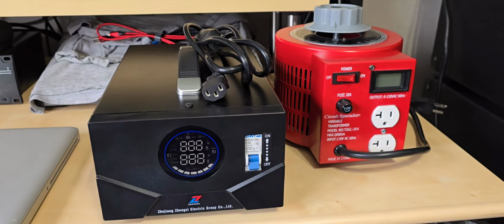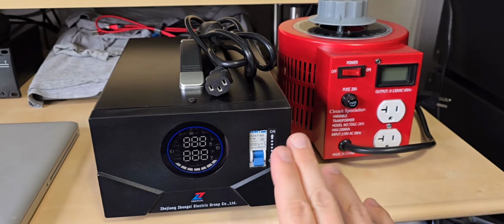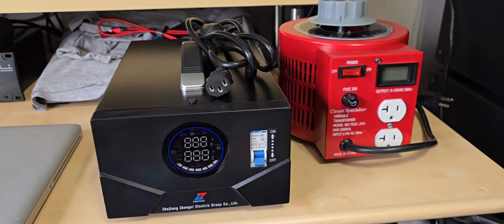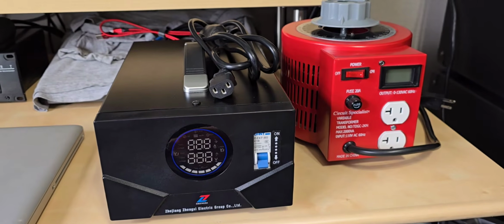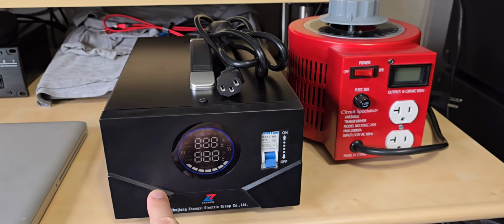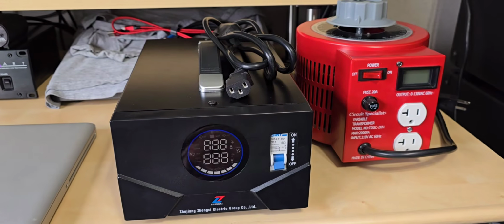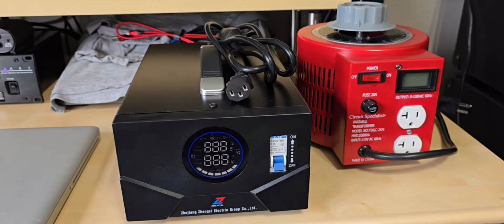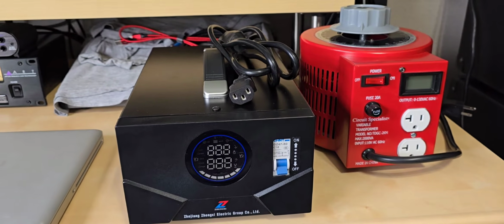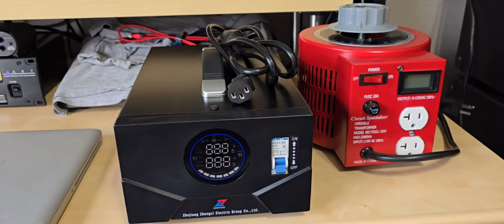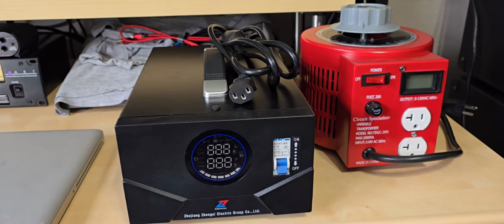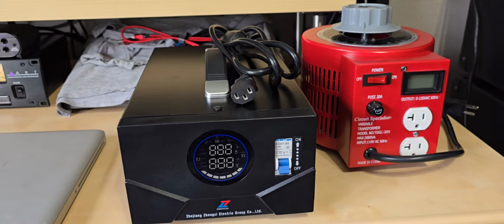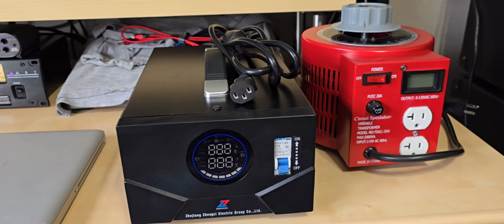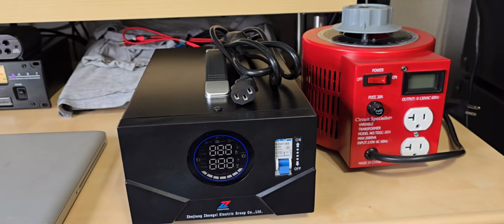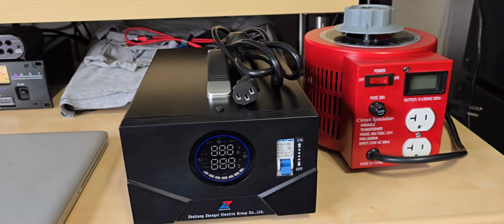I'm very happy now with the functionality because it is now working as described and advertised. To be fair, the 145 and 35 volts is considered voltage regulation, although it's not really effective in my opinion. The 132 and 105, as I mentioned, is a lot more reasonable because that's usually the upper and lower limits for any device that's only set to work at 120 volts.